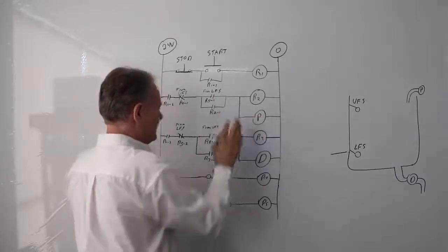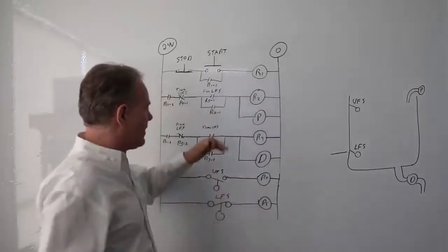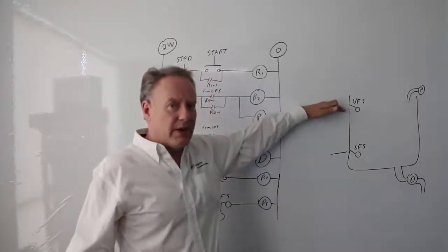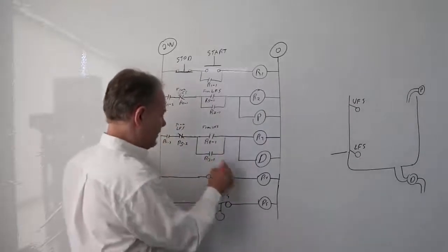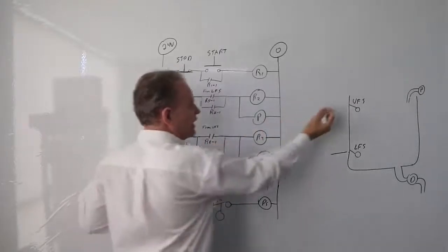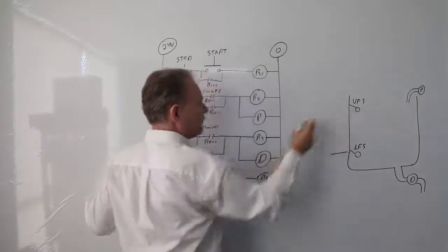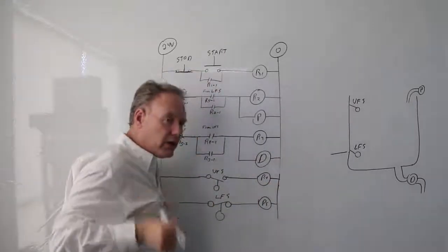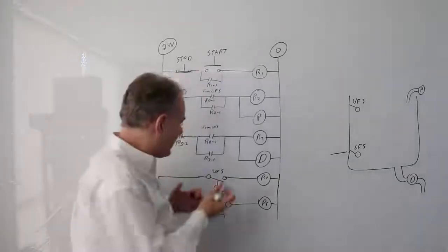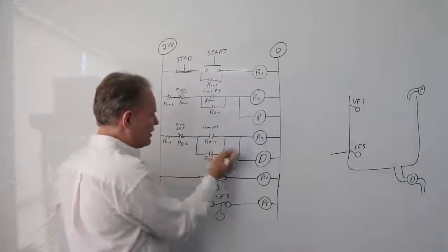So I'm latching onto that. Same thing's going on here when it's emptying. That's my drain cycle. The drain cycle starts when it gets up here, but I can't just use my upper float switch without latching onto it, because as soon as the liquid goes below the lower float switch, that event will make this contact become open. So I need to latch onto that.